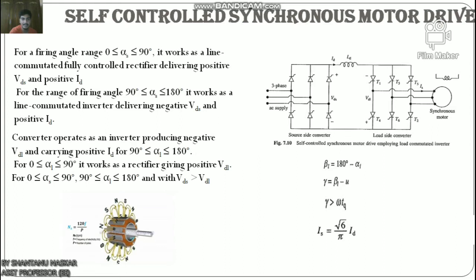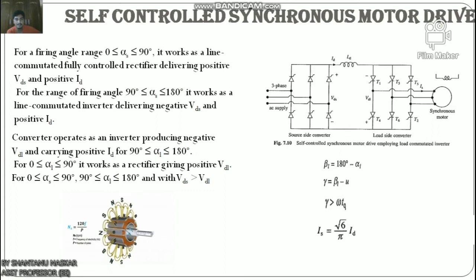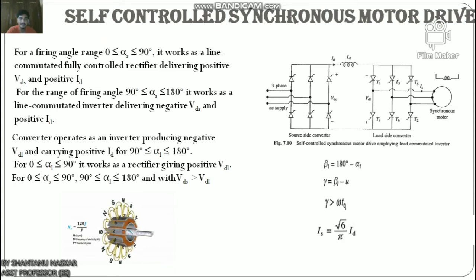Alternatively, firing pulses are generated by rotor position sensors, which are stationary and suitably aligned with the armature winding. The frequency of induced voltage depends on the speed of the rotor field, and the phase depends on the location of rotor poles with respect to the armature winding. Signals generated by rotor position sensors have the same frequency as the induced voltage with a defined phase relationship. Load-side converter thyristors are fired in sequence with 60° intervals; therefore six rotor angular positions per cycle of induced voltage are required. Hall-effect sensors detect the magnitude and direction of the magnetic field — three Hall-effect sensors can detect all six rotor positions. The sensors are mounted at 60° electrical intervals and aligned suitably with the armature winding.